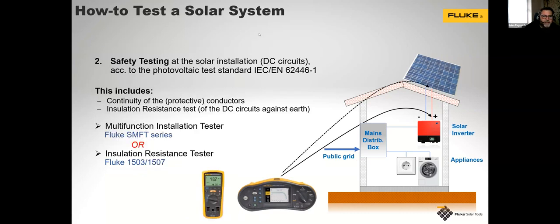The next thing we need to do is start moving to the solar installation, the DC circuits, and the photovoltaics test standard for that is 62446-1. You're probably going to be very bored by the end of this with all of the IEC regulations that we're looking at, and this includes continuity of the conductors, insulation resistance test. We can use a multifunction installation tester. We can use the Fluke SMFT series, or the solar tester, or we could use an insulation tester such as the Fluke 1503 and 1507.